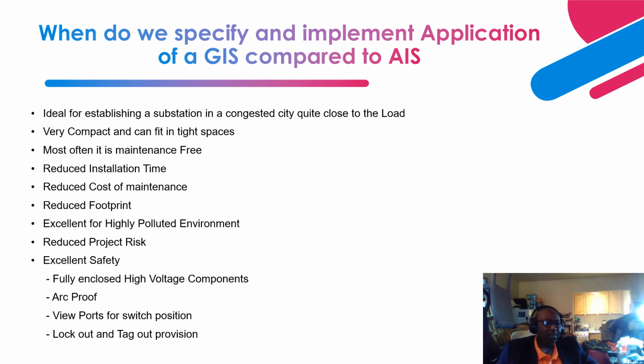Next is reduced project risk, and that is true. In a construction environment, you are installing a GIS, and you are able to achieve a reduced installation time because it comes in the form of modules. So you're able to reduce the project risk in meeting due dates, and also the budget. You're able to meet the required budget, compared to an AIS substation. Next is excellent safety. Because everything is in a metal enclosure, all the live parts are fully enclosed and not accessible to operating personnel or maintenance personnel. So it offers excellent safety for personnel that come into close proximity with this component.